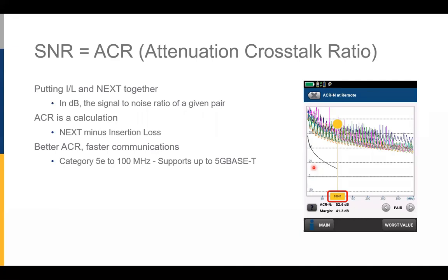Now, they came out more recently with even some higher speeds than gigabit Ethernet. They call these NBASE-T, and that can be either 2.5 or 5 gigabit Ethernet. Now, when they developed 2.5 and 5 gigabit Ethernet, they really wanted them to work on category 5E cable. There's more category 5E cable installed than anything else. So those will run on category 5E cable. You can get up to 5 gigabit Ethernet. That is a lot of bandwidth.